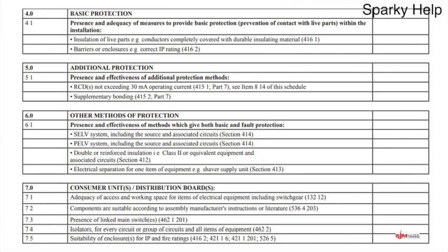Typically domestic, that's what you can have. You can have them everywhere. Obviously it's probably the main ones you'll come across. But there are a couple of others that you've got: placing out of reach and obstacles could also be used, but they can't be used in domestic premises. So what we're checking for within your installation is, is all the installation intact and can you touch any live parts whatsoever? If you can't, then it will be a tick. Obviously, if you've done something wrong, if you could, then not.